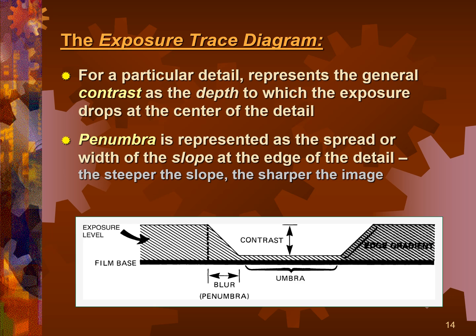because it's got an edge that you are not mapping to a single location on the image receptor. You're actually spreading out that edge over basically something proportional to the focal spot size times the OID over SOD ratio, OID to SOD ratio.